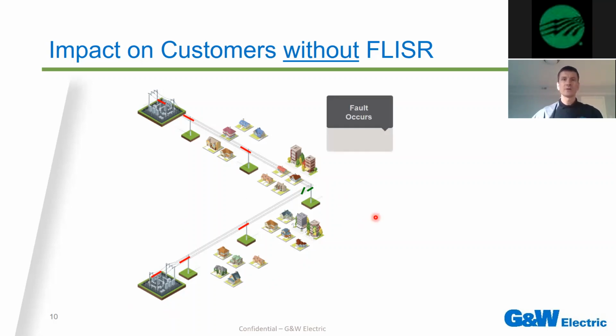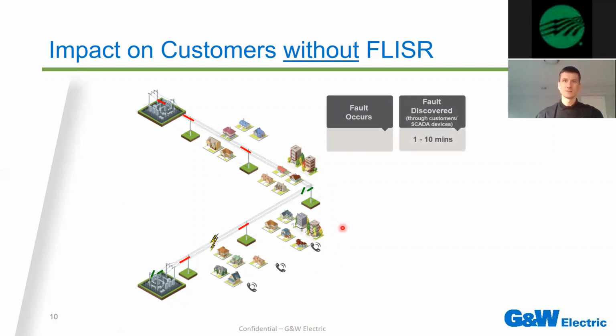So now we have a fault occurring in this little simulation here, and we have this fault occurring here in the south. As a first operation, the substation breaker trips and essentially isolates this entire section down here. Then you most likely would get calls from these customers, all of them affected by this fault, anywhere between 1 and 10 minutes. And don't hold me to those times here. It's just to get the point across of the differences with and without FLISR.